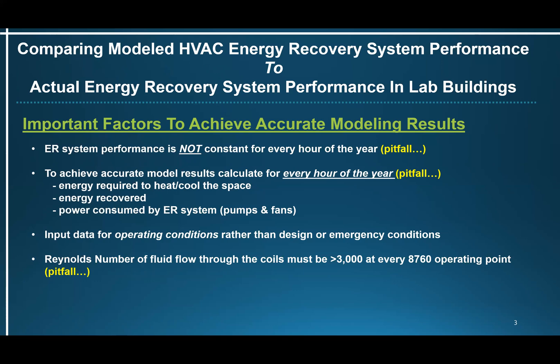To achieve accurate model results, calculate for every hour of the year: the energy required to heat or cool the space, the energy recovered, and the power consumed by the energy recovery system — both pump power and the added fan power to overcome the air pressure drop through the energy recovery coils.